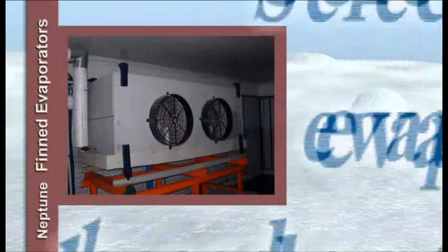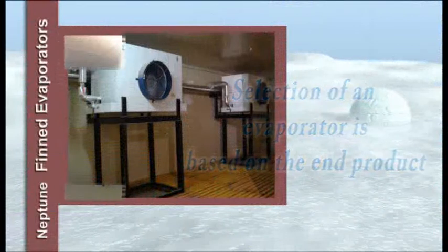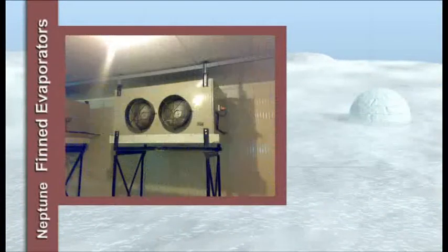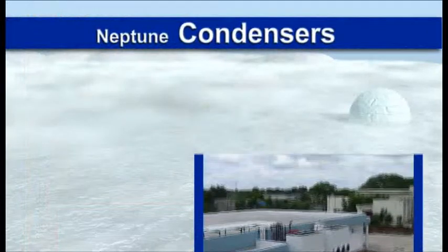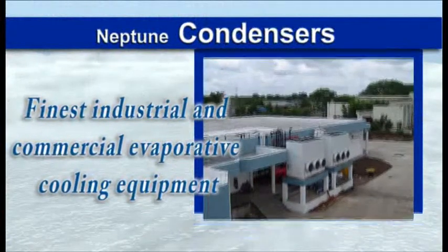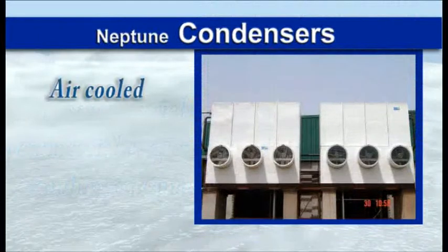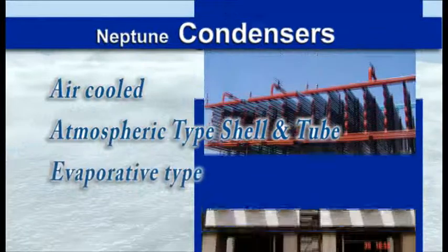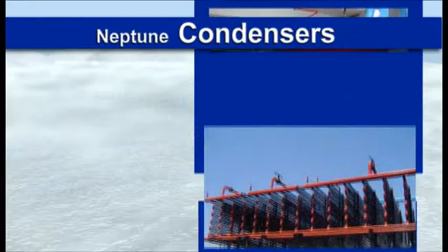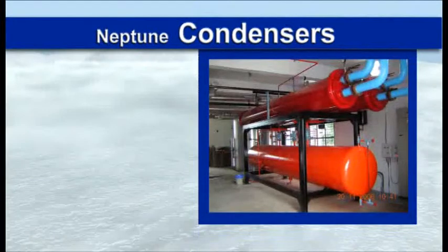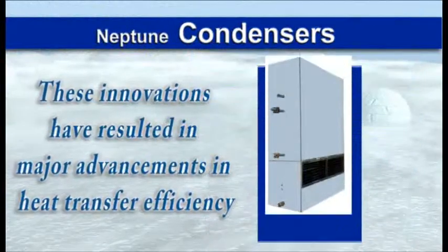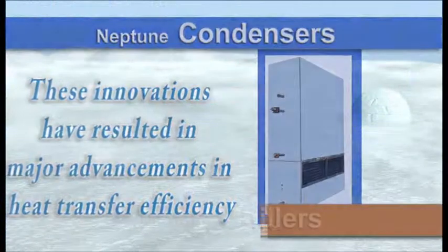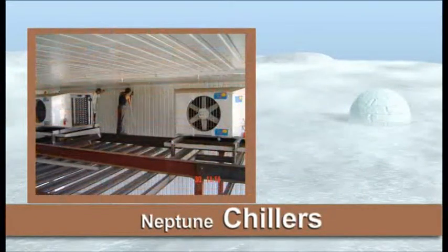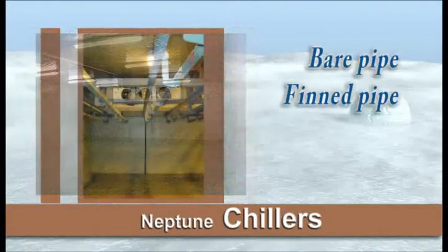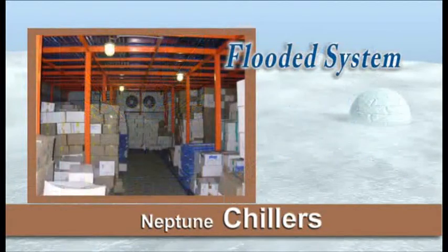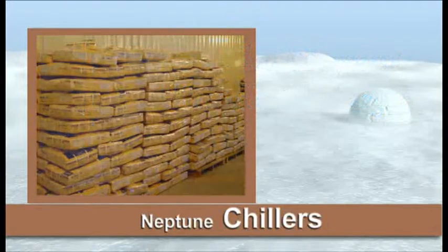Neptune finned evaporators. The selection of an evaporator is based on the end product for which the whole refrigeration plant is designed. There are finned type air cooling units for cold storage. Neptune condensers. Neptune is dedicated to providing the finest industrial and commercial evaporative cooling equipment. There are different types of condensers, namely air-cooled, atmospheric type shell and tube, and evaporative type. Evaporative type condensers are the most efficient. Neptune's research has resulted in many condenser innovations. These innovations have resulted in major advancements in heat transfer efficiency. Neptune chillers. Neptune manufactures chillers of various types like bare pipe, finned pipe, shell and tube, direct expansion, flooded system, and plate heat exchanger. Proper design ensures maintenance of correct temperature of the product.